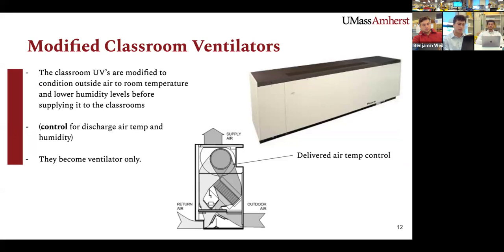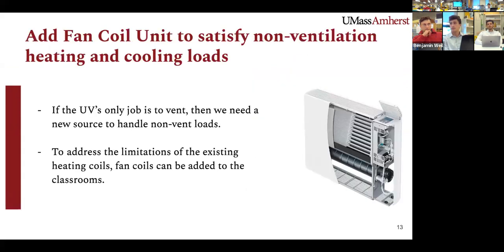If we want to lower the temperature of the water our system uses, we have to ask the unit ventilator to just do less. This means the one job the unit ventilator would have would be to temper ventilation air, or just become a ventilator only. This can be achieved by delivered air temperature control. If the unit ventilator's only job is to vent, then we need a new source to handle non-ventilation loads and to address the limitations of the existing heating coil. Fan coils can be added to the classrooms.